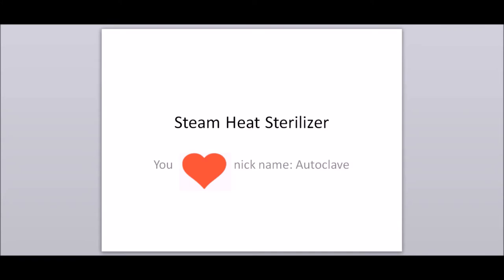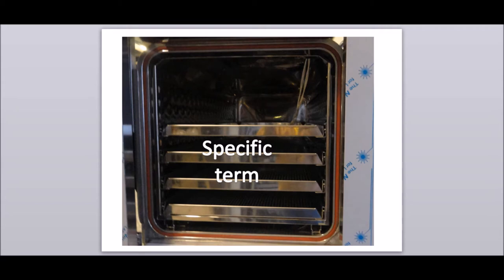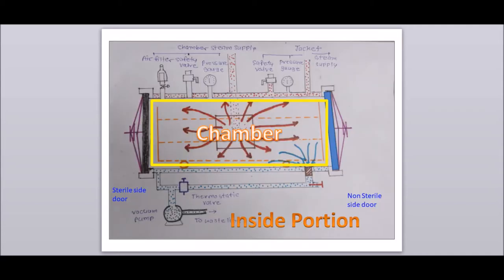In this video, we are going to understand the steam heat sterilizer, generally called autoclave. Some specific terms are used during cycle design, development, qualification, and during routine operation. The chamber is a main part of the autoclave that contains the item to be sterilized. The chamber is pressure tested during manufacturing, generally at a higher pressure than the operating pressure.